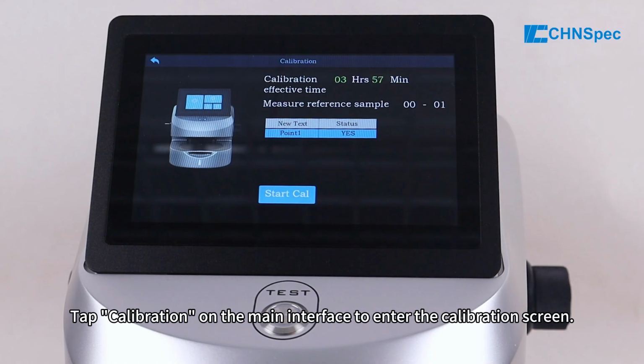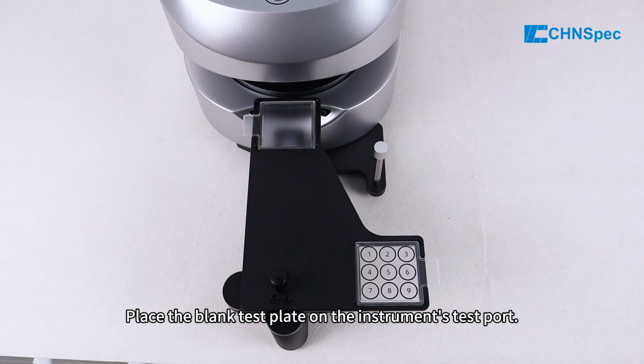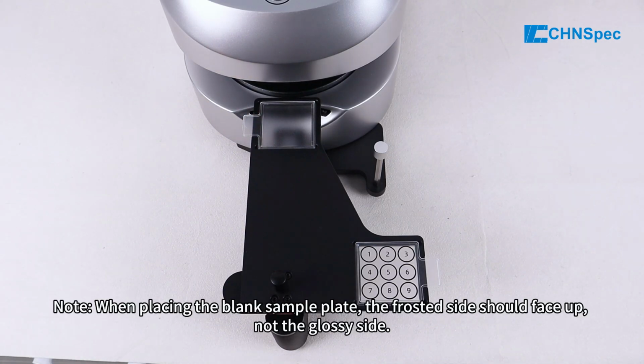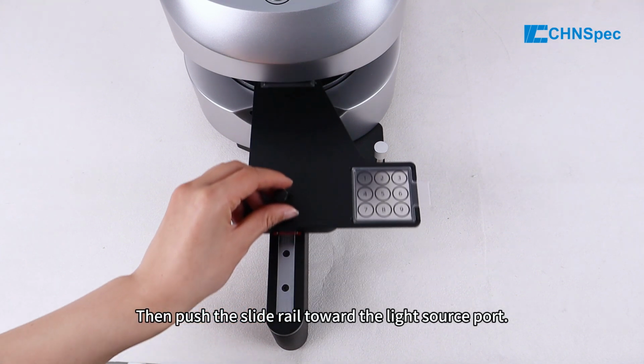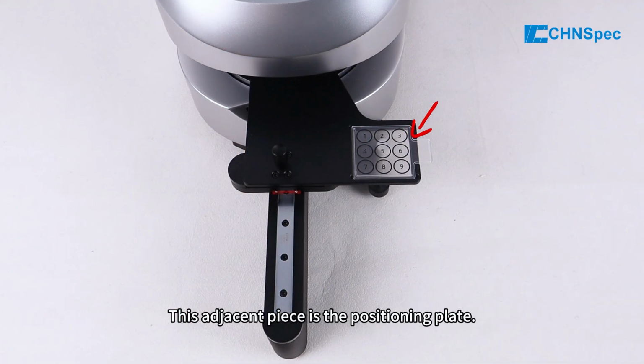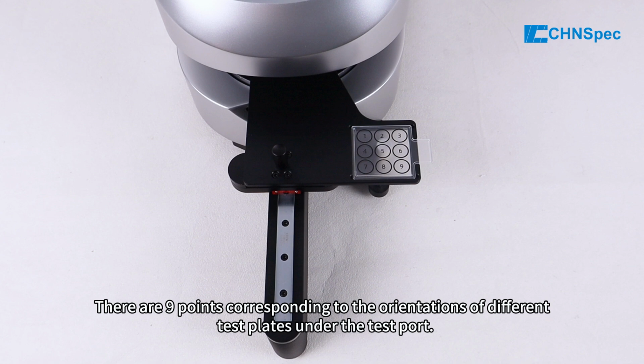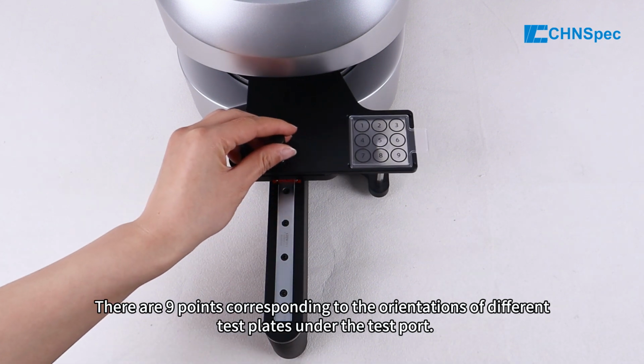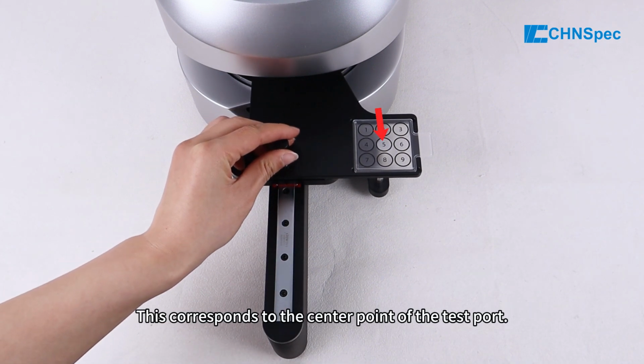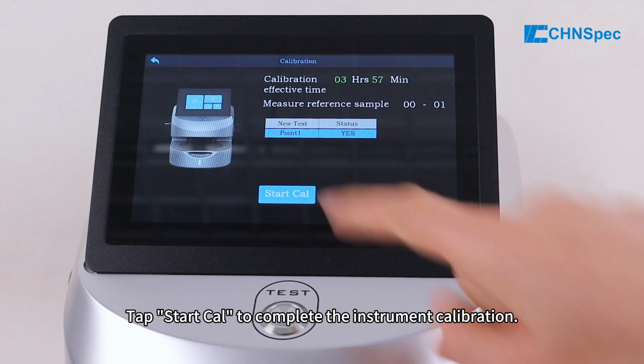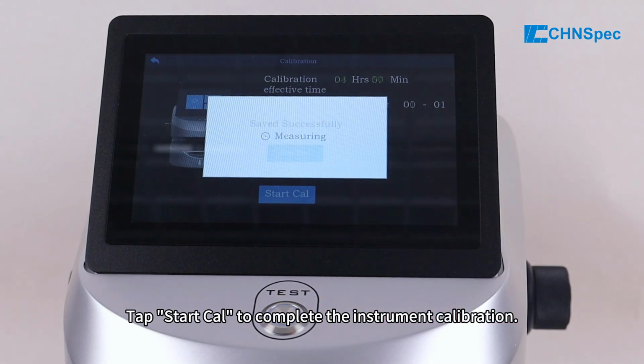5. Calibration. Tap Calibration on the main interface to enter the calibration screen. Place the blank test plate on the instrument's test port. Note, when placing the blank sample plate, the frosted side should face up, not the glossy side. Then push the slide rail towards the light source port. This adjacent piece is the positioning plate. There are 9 points corresponding to the orientations of different test plates under the test port. This corresponds to the center point of the test port. Tap Start Cal to complete the instrument calibration.